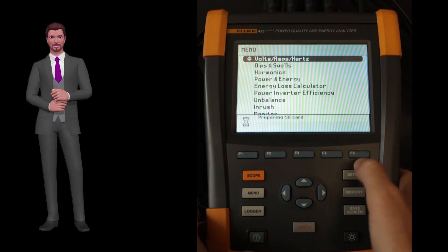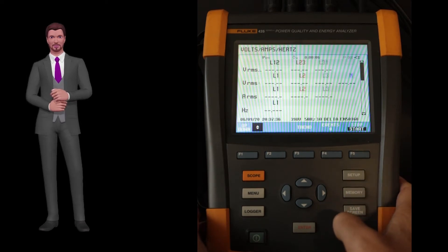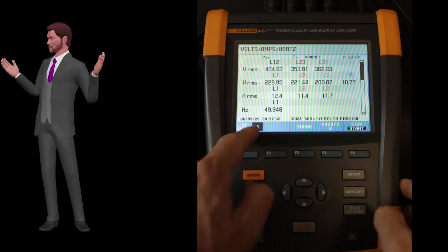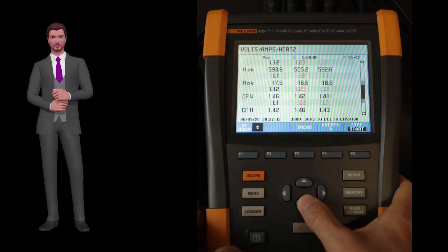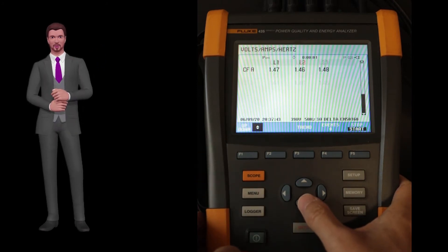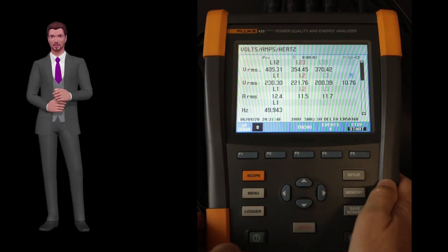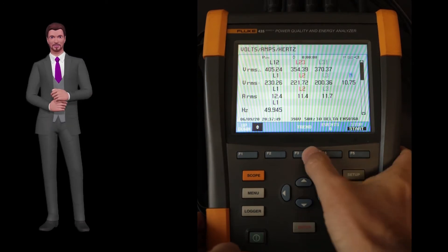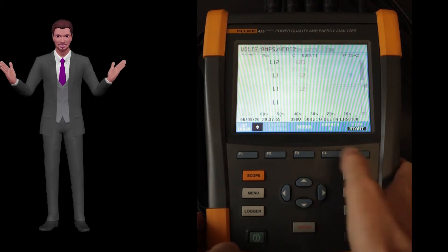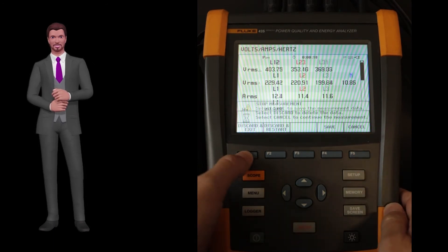Let's now quickly see what each of these functions does. The volts, amps, hertz function allows us to measure and record basic parameters such as voltages, currents, frequency, peak voltages, and peak amps. Since it is not always possible to view all the parameters on the instrument screen at the same time, using the up and down keys it is possible to scroll the screen to see all available parameters.